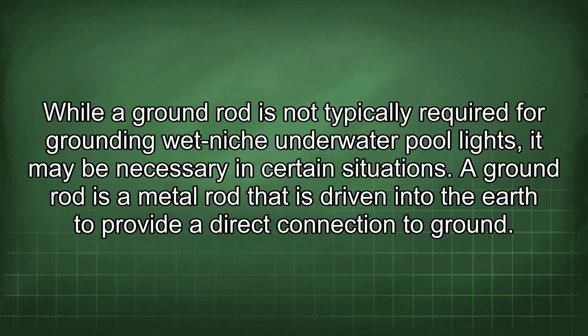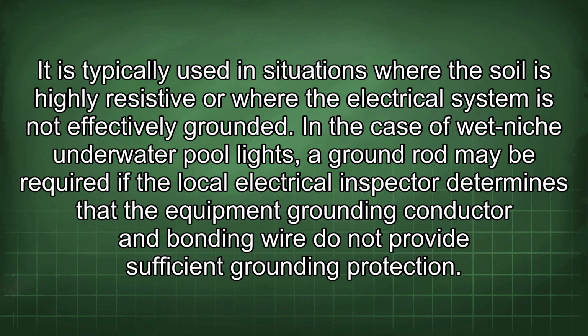While a ground rod is not typically required for grounding wet niche underwater pool lights, it may be necessary in certain situations. A ground rod is a metal rod that is driven into the earth to provide a direct connection to ground. It is typically used in situations where the soil is highly resistive or where the electrical system is not effectively grounded. In the case of wet niche underwater pool lights, a ground rod may be required if the local electrical inspector determines that the equipment grounding conductor and bonding wire do not provide sufficient grounding protection.